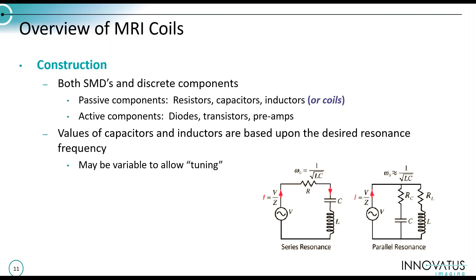A challenge with MRI coils is that they're not really conducive to field-based repairs. OEMs such as GE, Siemens, and Philips do not provide schematics for end users or service engineers. If you wanted to do some investigation, you're going to have to develop schematics as well as test procedures on your own. The OEMs just don't get to that level of granularity on this type of device. Coils, as well as ultrasound probes, are almost viewed as accessory devices by an OEM, even though they're their own class 2 medical device. You definitely need some specialized tools and test equipment.